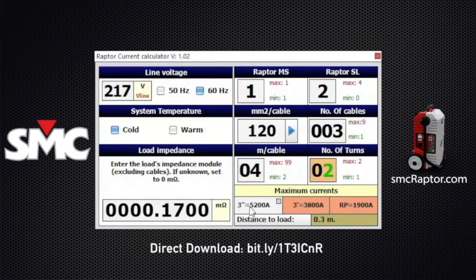What we're seeing here in 3 seconds, 3 minutes, and permanent duty cycle, when you see the red for any length of time, is going to increase the thermal or exceed the temperature on the cable itself. So this is a perfect tool to manipulate and play with, even allowing you to decide what needs to go out into the field before you load up the truck or van, telling you whether you need just the main Raptor system, or do you need to take 1, 2, or more 5 kVA slaves along with you?